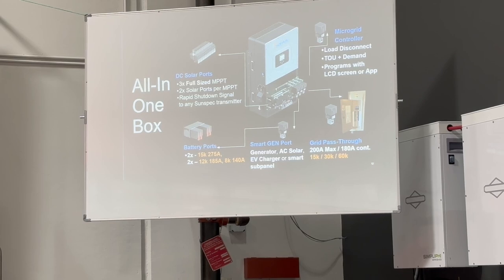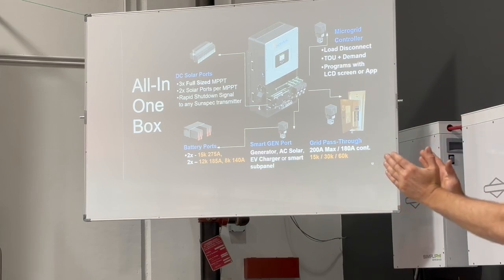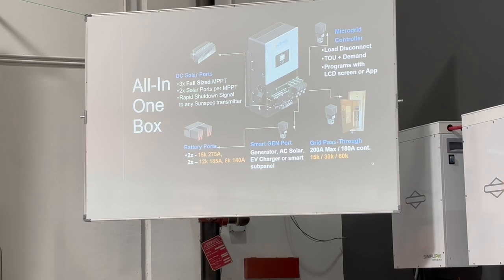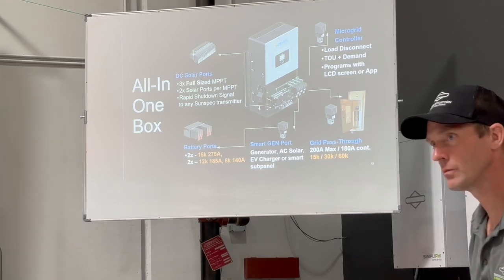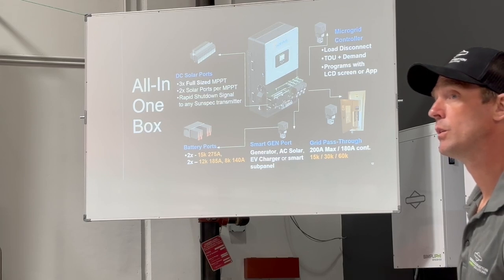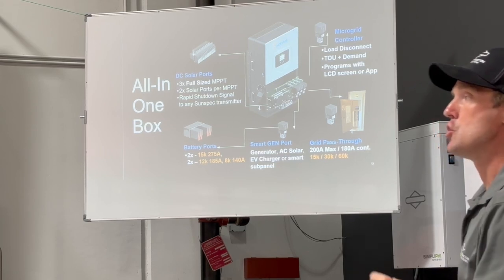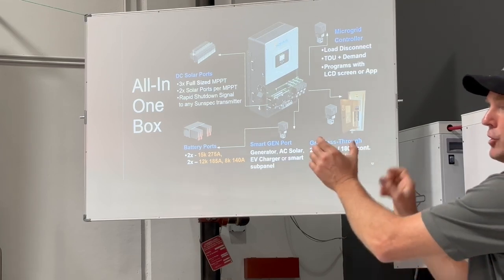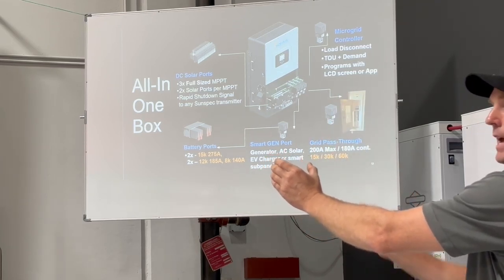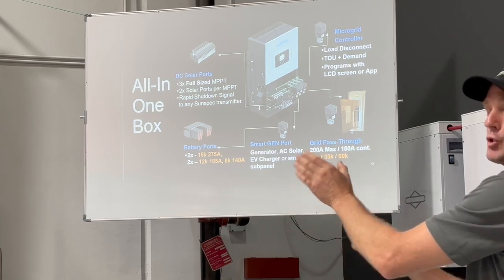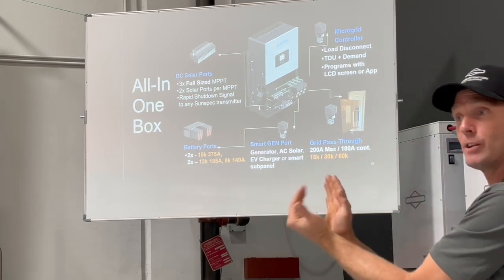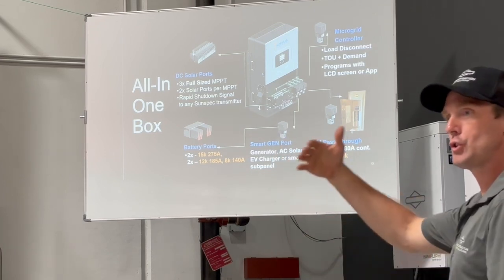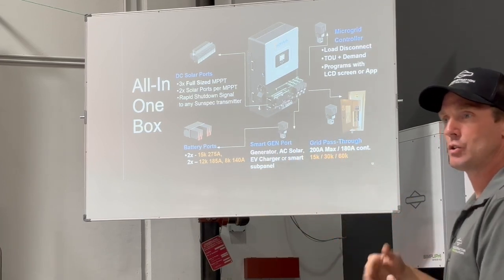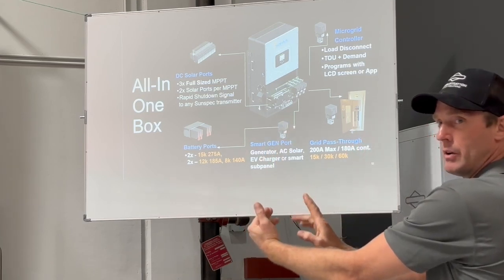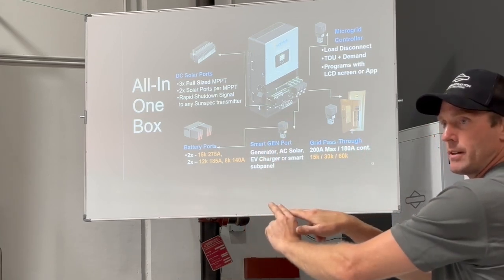That's the first 2 ports only, right, and the other 2 you can have for batteries? You have 2 ports for 1 MPPT, and then the next one, 2 and 2. The second one, from what I heard, you can go to batteries, and you can balance the voltage, you don't have to have the same voltage for the second MPPT. Yeah, the first set of panels does not have to match the voltage of the second set of panels. I was just talking about 2 strings combined into a single input. You have 3 independent inputs, 2 sets of clamps per input. So when you use input number 1, match the voltages on the panels that are both going into that input number 1.